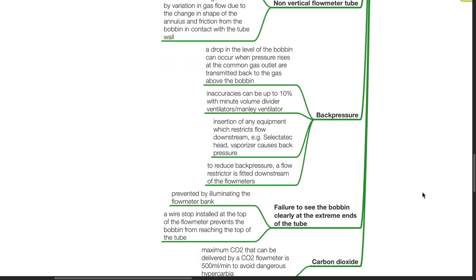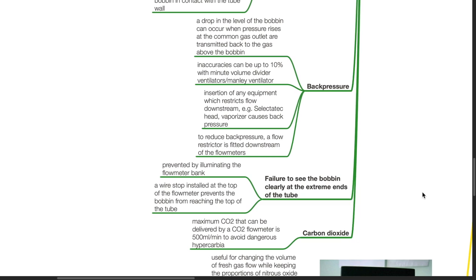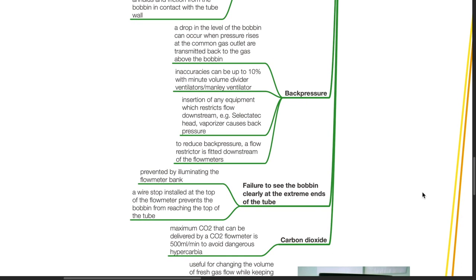Back pressure: A drop in the level of bobbin can occur when pressure rises at the common gas outlet transmitted back to the gas above the bobbin. Inaccuracies can be up to 10% especially with minute volume divider ventilators or Manley ventilator.